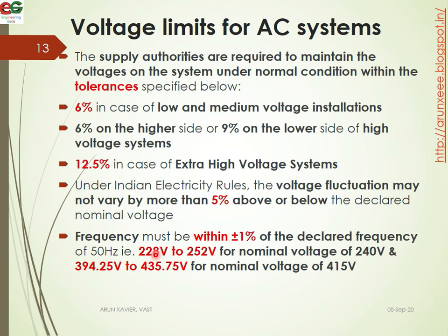The standard frequency is 50 Hz. For example, if the nominal voltage is 240V, the allowable range is from 228V to 252V. For 415V systems, the allowable upper limit is approximately 435.75V, accounting for the specified tolerance percentages.